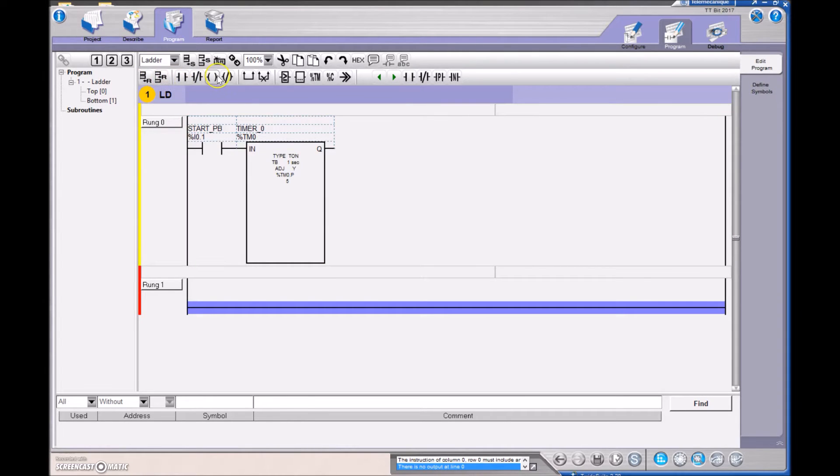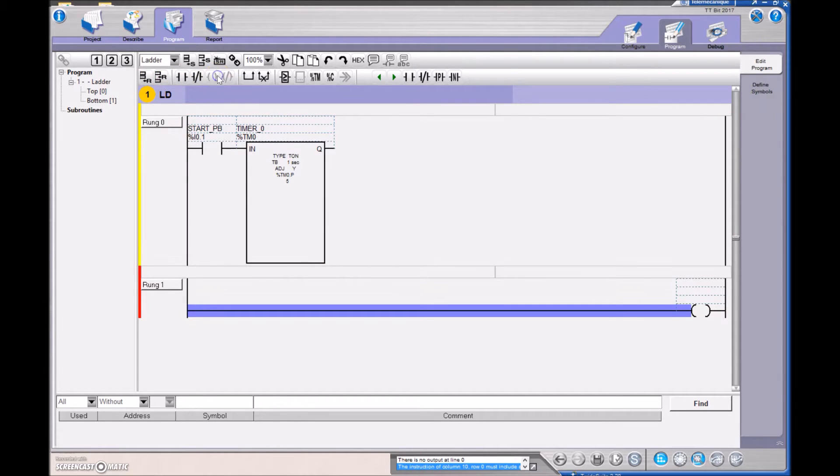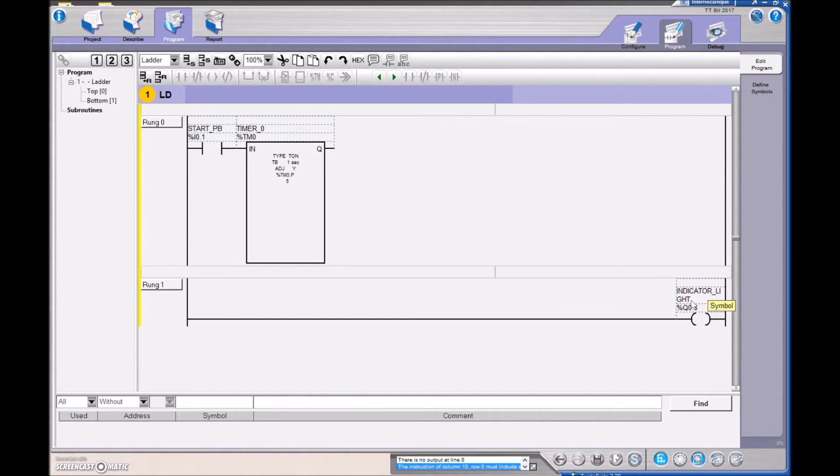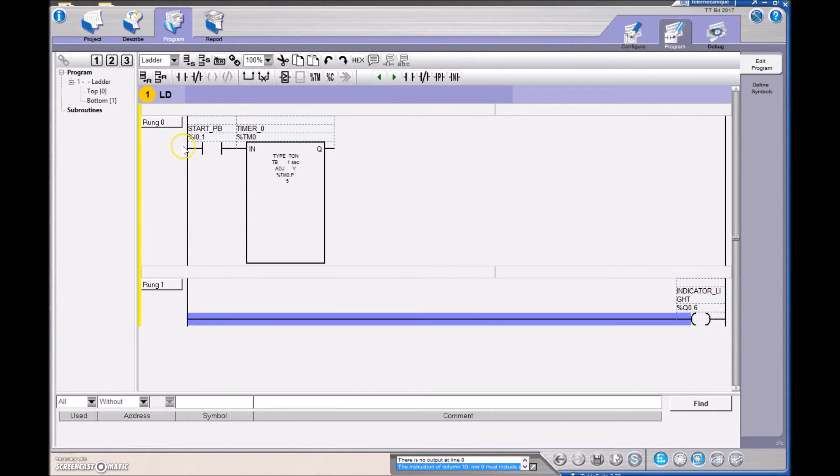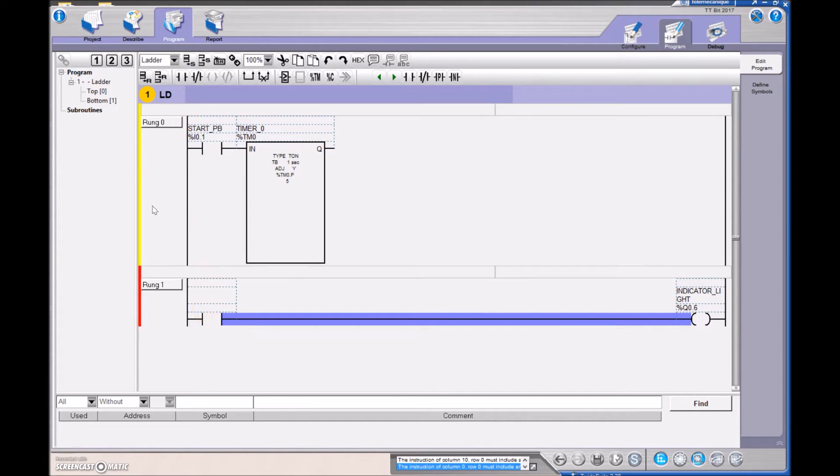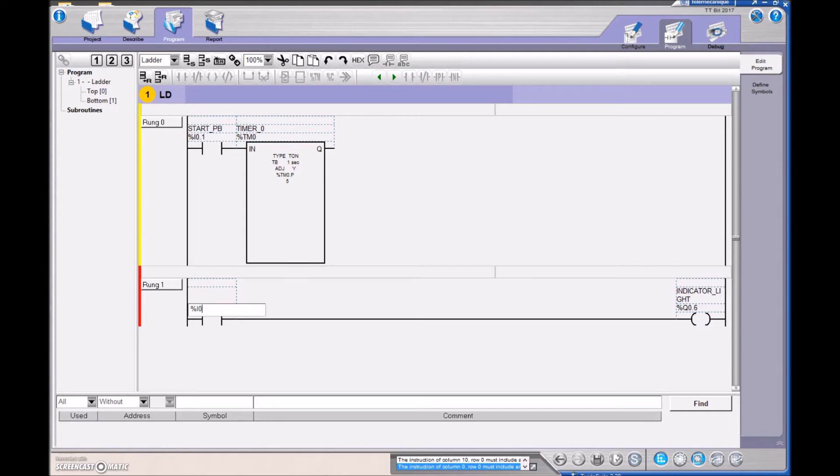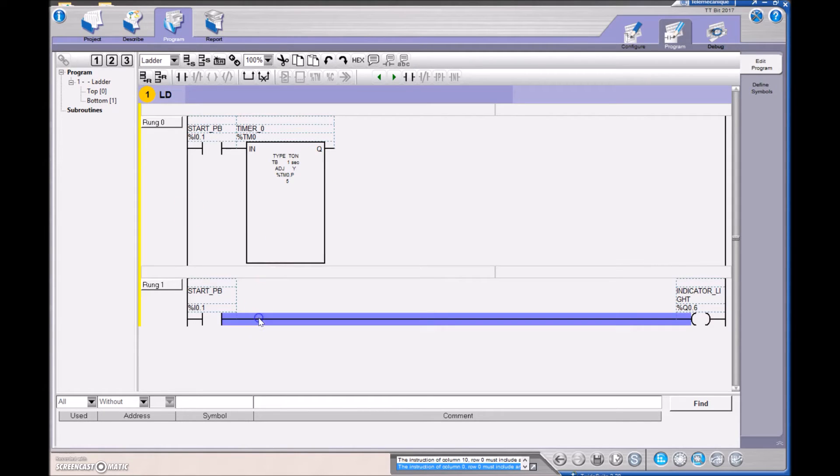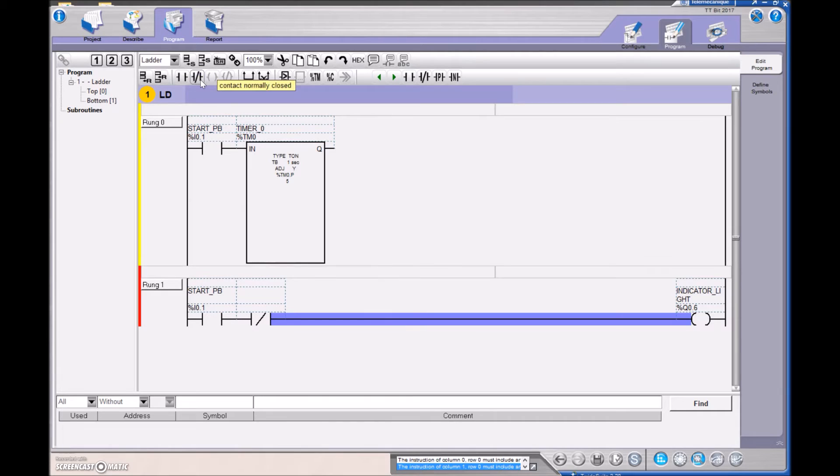And I want two instructions to turn on my indicator light. My indicator light I physically wired to output number six. And what I want to do is I want to be able to hit the push button. So there's my push button there. Let's just address that, input 0.1. And I also want the output. So if I hover here, you can see that Q is the output of the timer. I want the output to not set yet. So right here, I'm going to drop in an examine if open, or look for a 0.